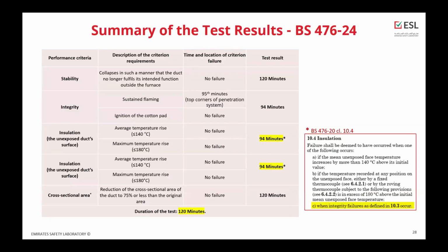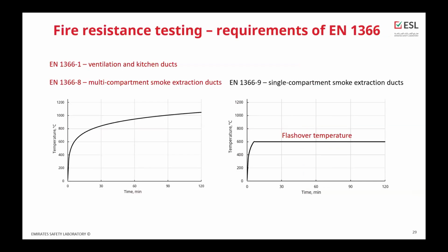This is how the test results are presented. You can see that integrity and insulation have the same test results, even though insulation was not failed. But this is because of the regulation of BS 476 Part 20, where there is information that insulation is also failed once the integrity is failed.